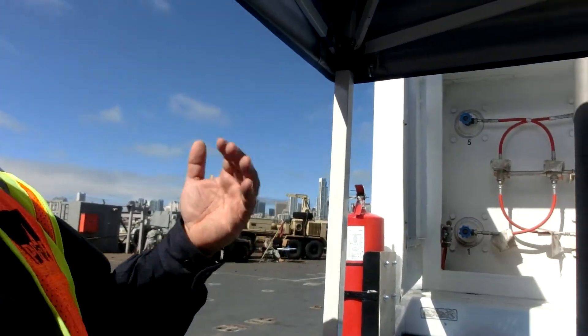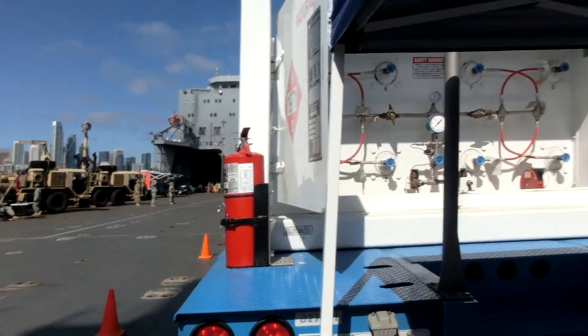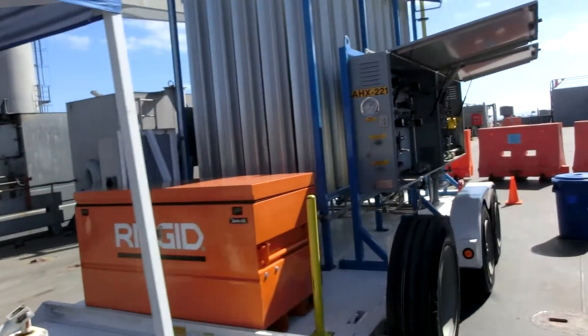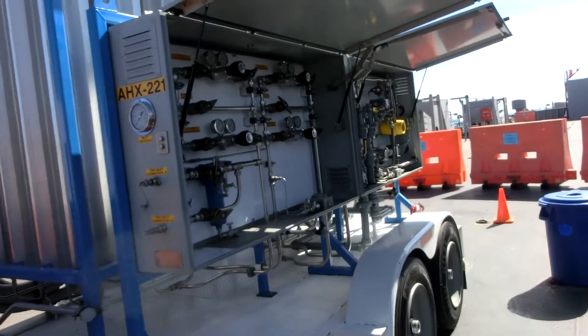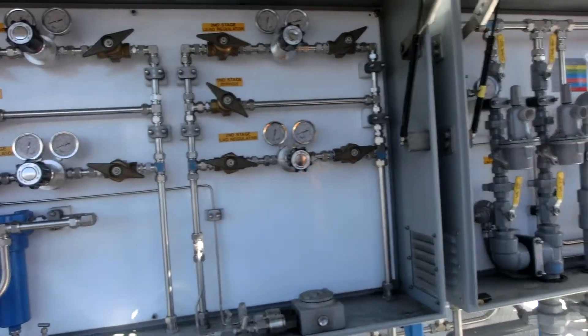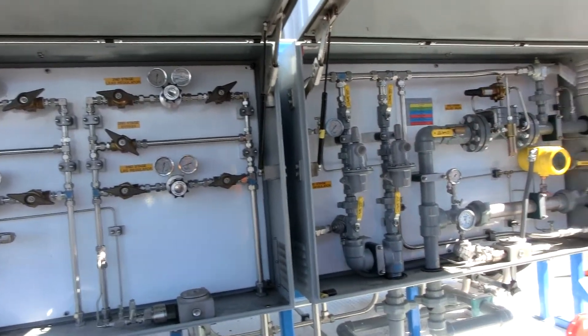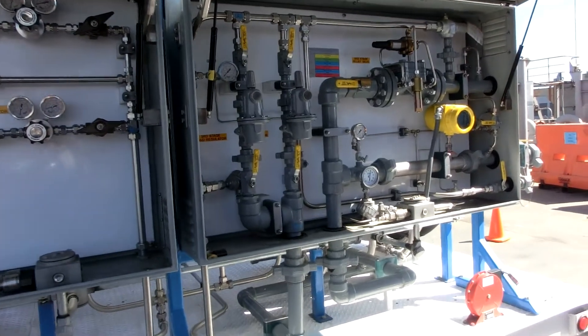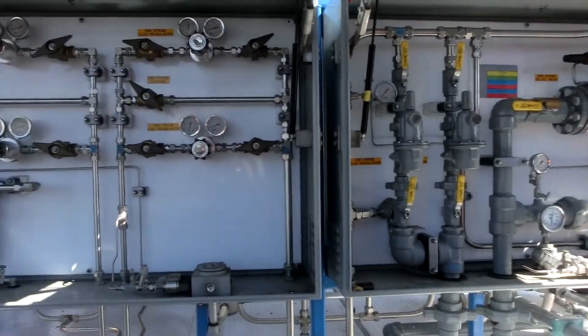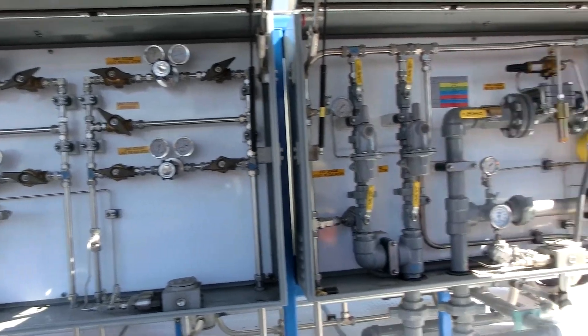We basically operate on pressure demand because it's 2400 pounds and our pipeline system is 50 PSIG. We need to go through a pressure letdown — what we call three stages of regulation. We start with a pressure cut from 2400 pounds down to maybe 700 to 800 pounds.